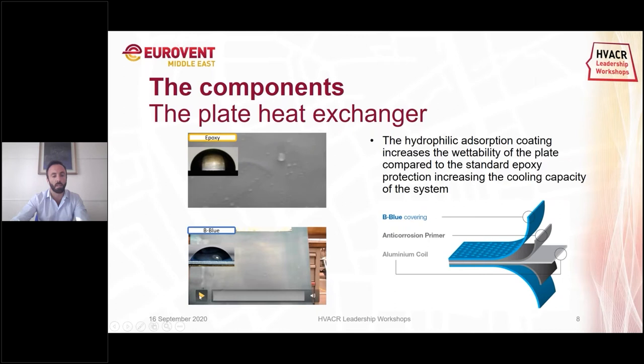In the video below, there is a coating called 'B-Blue' that can increase the performance of the whole system. This coating is able to retain the water — as you can see — and also spread it, creating a thin layer of water on the surface. In our lab at the University of Milan, we have seen an increase in performance of over 10 percent with this coating.